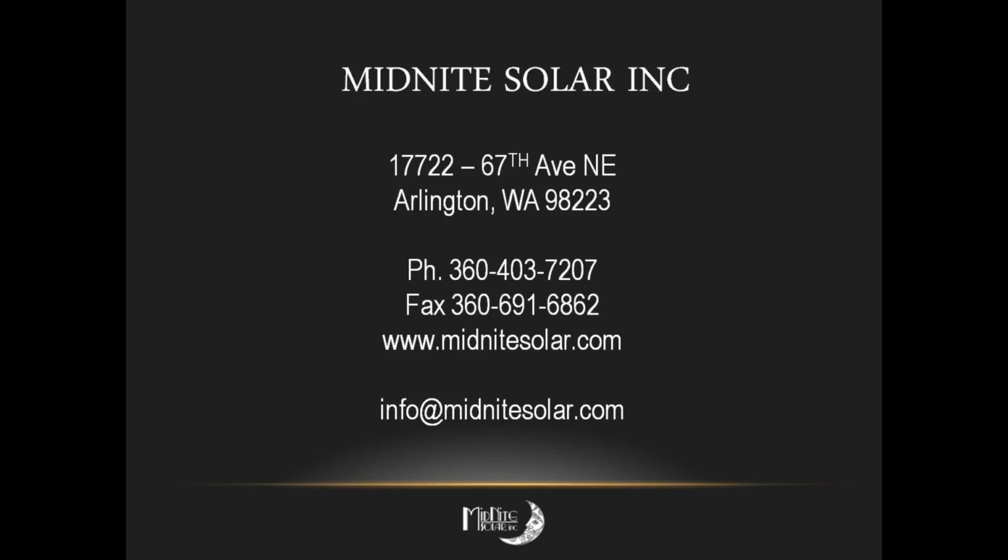Okay, I'm being told that 110.14 C, I'm thinking that's 110.14(C), does not allow free air rating. I will have to look into that. Maybe they can clarify that because it says 110.14 right now. That one is in your camp. No, I will research that.